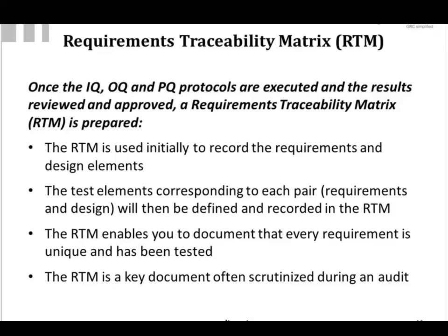The RTM allows you to make sure that every requirement is documented as a unique one and that it's been tested thoroughly. So it's a very key document during audit because it will demonstrate that you took the requirements, you said what the system purports to do, and you can demonstrate that a test was done against each of those requirements to make sure it's met.